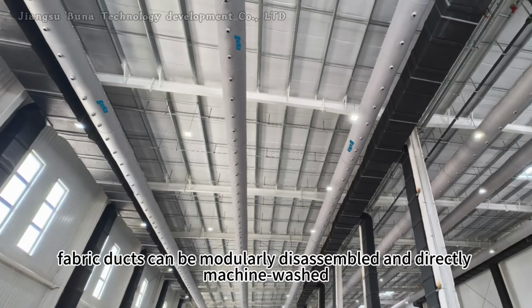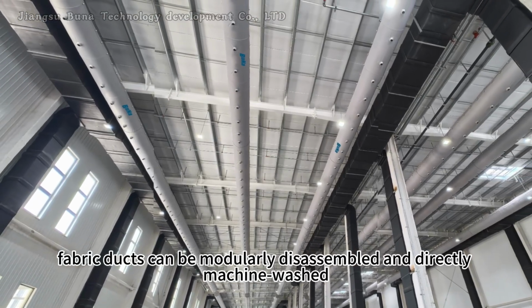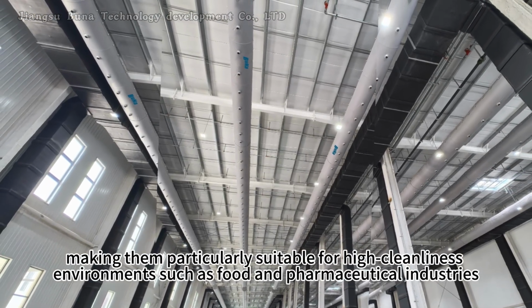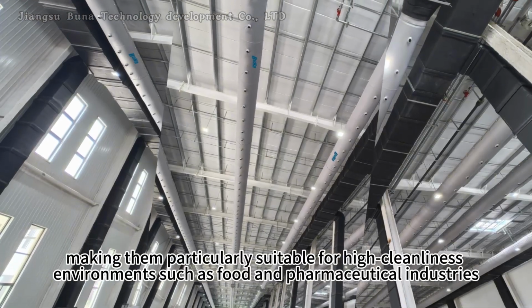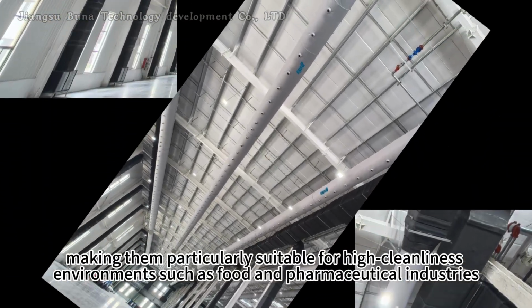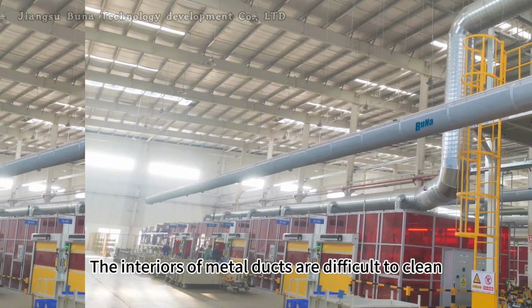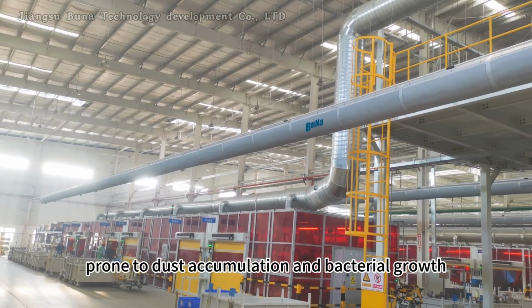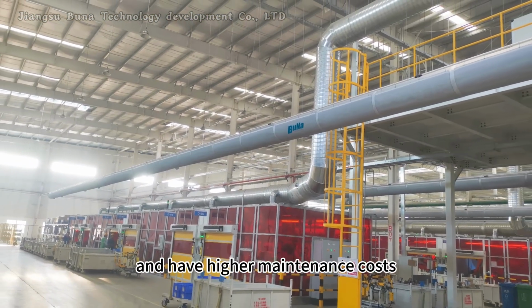In terms of maintenance and management, fabric ducts can be modularly disassembled and directly machine washed, making them particularly suitable for high-cleanliness environments such as food and pharmaceutical industries. The interiors of metal ducts are difficult to clean, prone to dust accumulation and bacterial growth, and have higher maintenance costs.